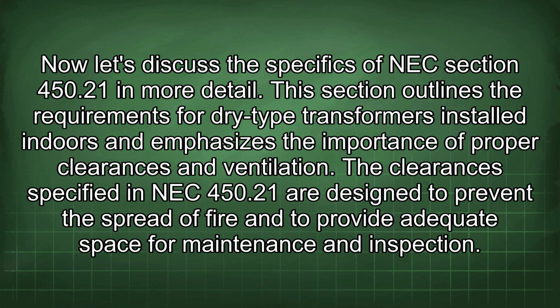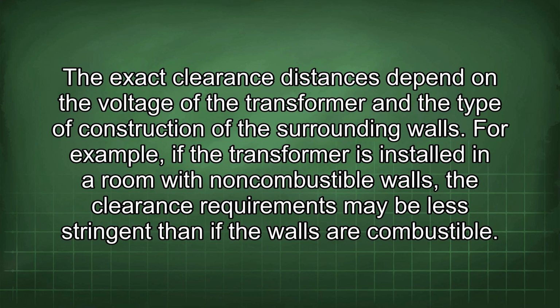Now let's discuss the specifics of NEC Section 450.21 in more detail. This section outlines the requirements for dry-type transformers installed indoors and emphasizes the importance of proper clearances and ventilation. The clearances specified in NEC 450.21 are designed to prevent the spread of fire and to provide adequate space for maintenance and inspection. The exact clearance distances depend on the voltage of the transformer and the type of construction of the surrounding walls. For example, if the transformer is installed in a room with non-combustible walls, the clearance requirements may be less stringent than if the walls are combustible.